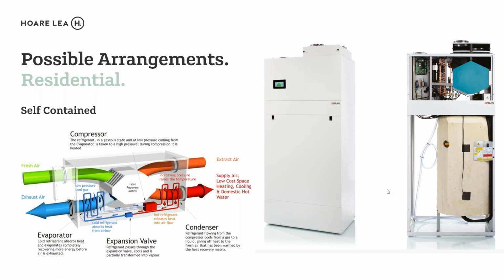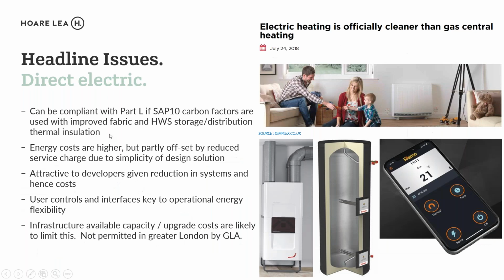And the elephant in the room is direct electric, because everyone will argue that if your electricity carbon content is so low, why aren't you using direct electric? And it can still pass Part L currently, in the current guise of Part L, if your carbon content is used. But you have to improve hot water storage and distribution, and the fabric performance, to do it. The energy costs are going to be higher because it's direct use, but you do actually reduce service charge. So it becomes a lot simpler installation and maintenance using direct electric. But in the scheme of things, it's not the best way to go with regards to carbon emissions. Even though the carbon content of electricity is decreasing, it's not the way to get effectively to net zero.